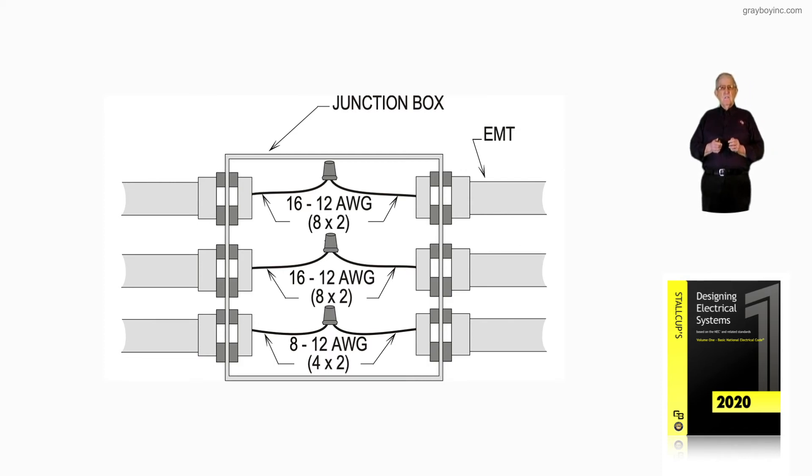Based upon what we have in this junction box, it's EMT with EMT connectors, and notice we have sixteen 12 AWG conductors. So there's two conductors there, one coming from the left, one from the right. So we'd have two times eight, and that would give us 16.